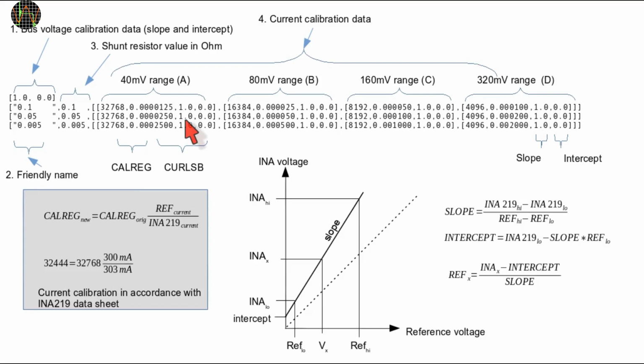The values shown here are needed even if you don't want to apply any real calibration. I think I mentioned that before. The choice of the word calibration by Texas Instruments is maybe a bit misleading. This is really mainly the configuration data, and it can be used for calibration as well. If you look at the formula that I selected for calibration, you realize that the default numbers of slope equal 1 and intercept equal 0 are such that the result x is always equal INA-x. In other words, no calibration. This is the reason why these values are set to 1 and 0.